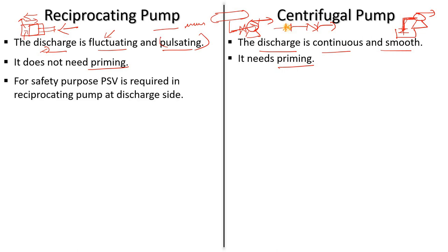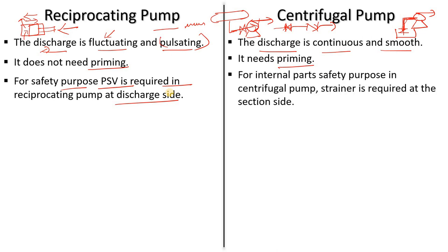For safety, a PSV (pressure safety valve) is required at the discharge side of a reciprocating pump. In a centrifugal pump, for internal part safety, a strainer is required at the suction side.